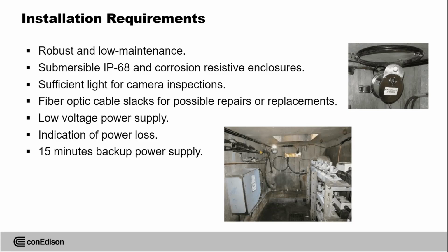We need to have sufficient light for camera inspection. If the manhole is completely closed, it's dark inside. When you light up the camera, that light, when it's on the top of the camera, may create reflection for the camera. So we solved it differently. We replaced this light with something else. Low voltage power supply we must have in each manhole, and indication of power loss, so that if power is lost, we have indication right away through the system so we can come and fix it, and 15 minutes of backup for the power supply.